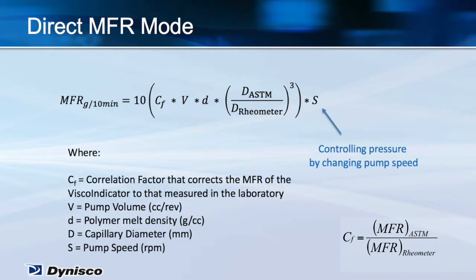Although the machine can control pump speed, enabling shear rate control, allowing viscosity measurements, we're going to talk about melt flow index testing. In direct MFR mode, pressure is controlled to the level that is equivalent to the weight used during the lab test. The pump speed required to maintain this pressure is the only variable in the equation that changes in real time, as you can see on the slide. Metering pump speed, pump flow rate, and melt density yield MFI directly as a function of pump RPM. In this bypass rheometer, the test polymer extrudes to atmosphere. As I said, it falls to the floor.